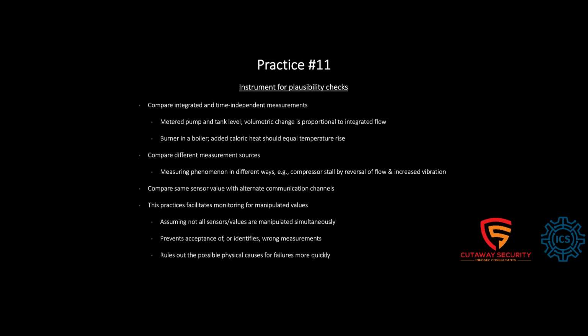These two things should be correlated. Something is wrong, maybe the device is out of calibration, or something is wrong with the device. That's one thing easily identified with this practice. And then it also rules out the physical causes of failures more quickly, because if you know that the flow meter is wrong, then you wouldn't suspect the valve, for example, right? Then you don't have to go inspect the valve in the field thinking maybe the valve is out of calibration.